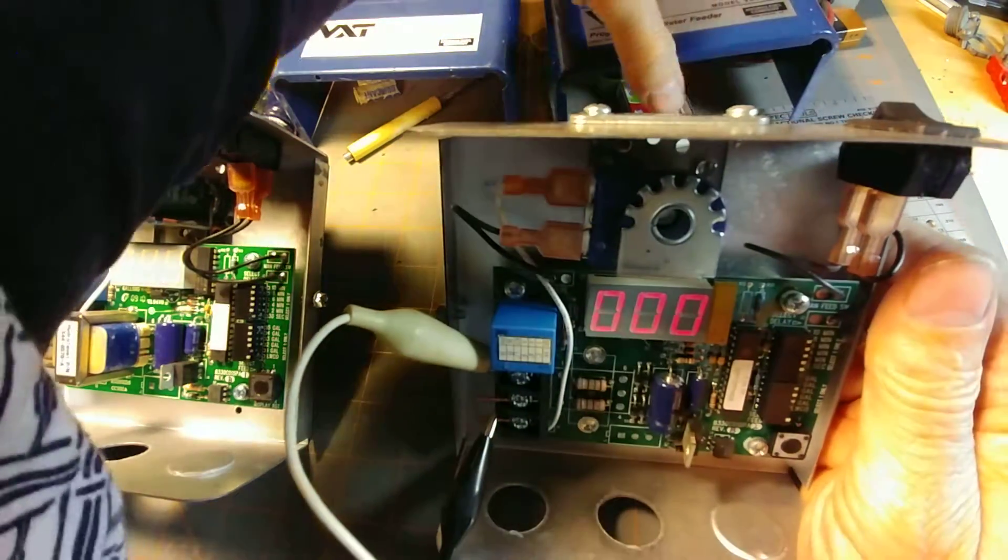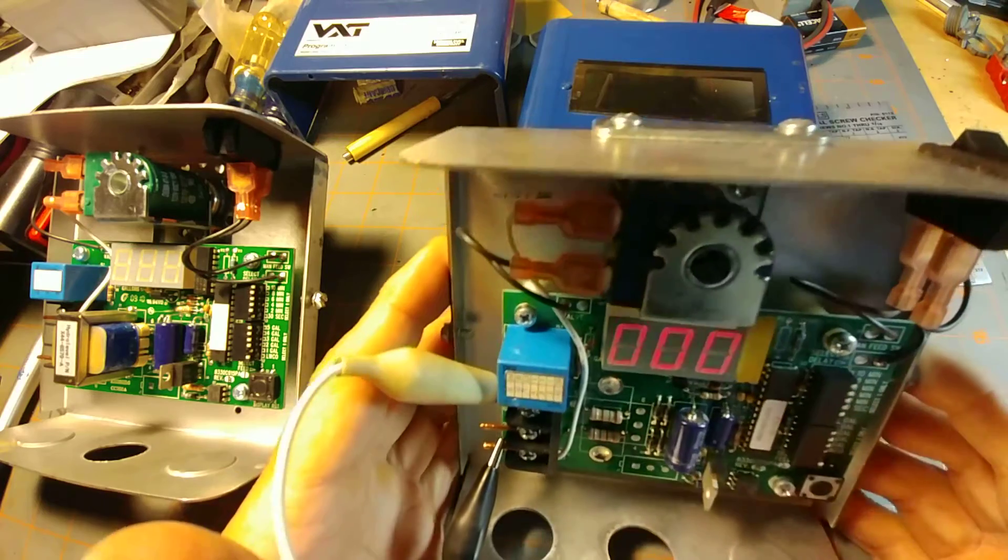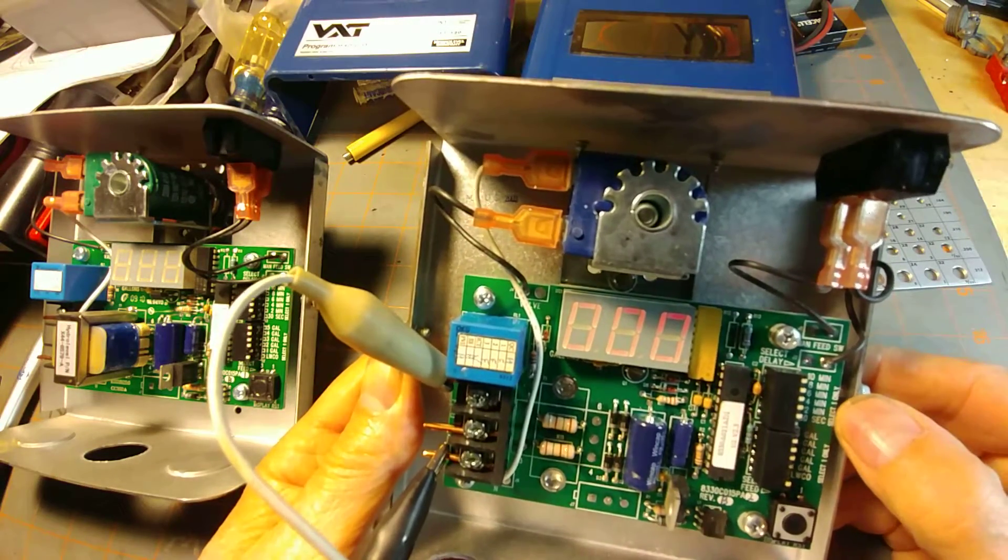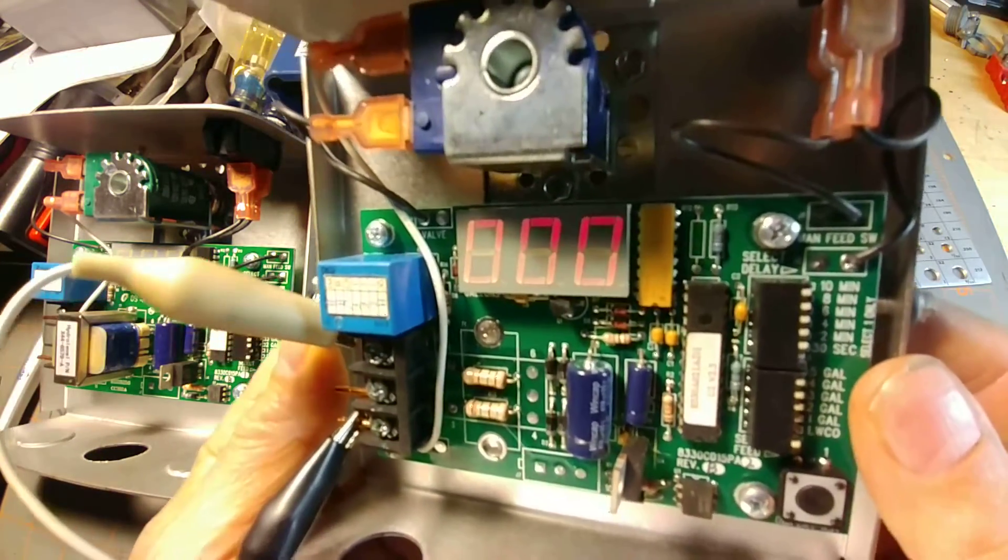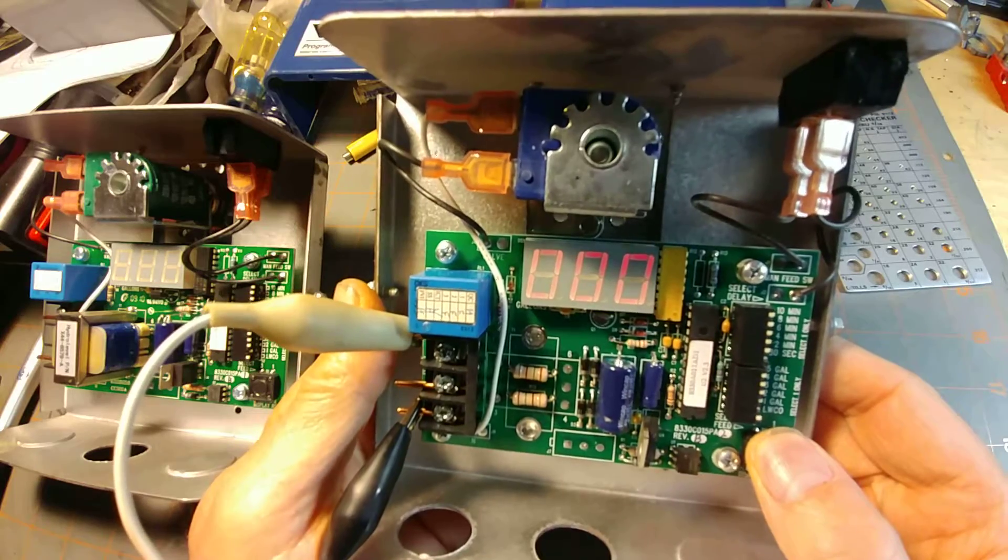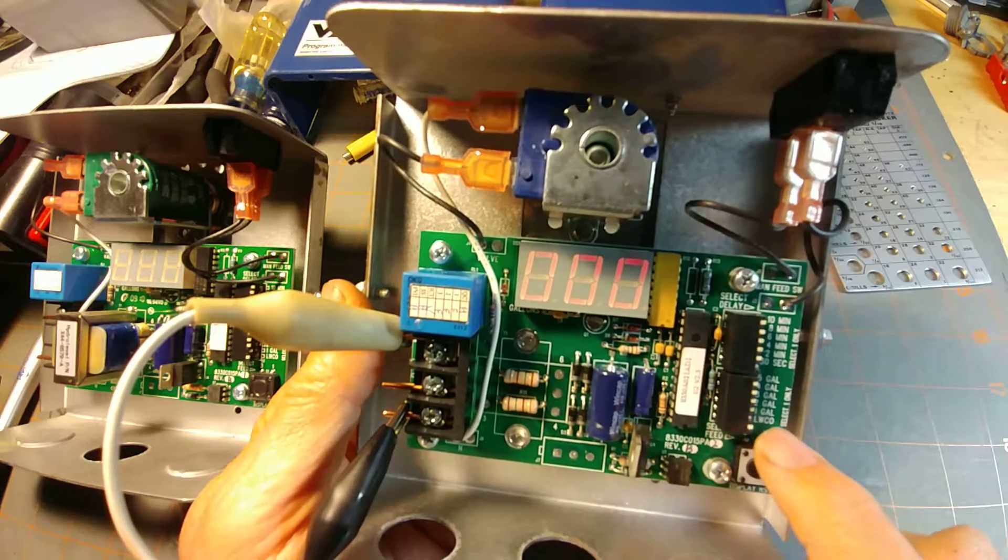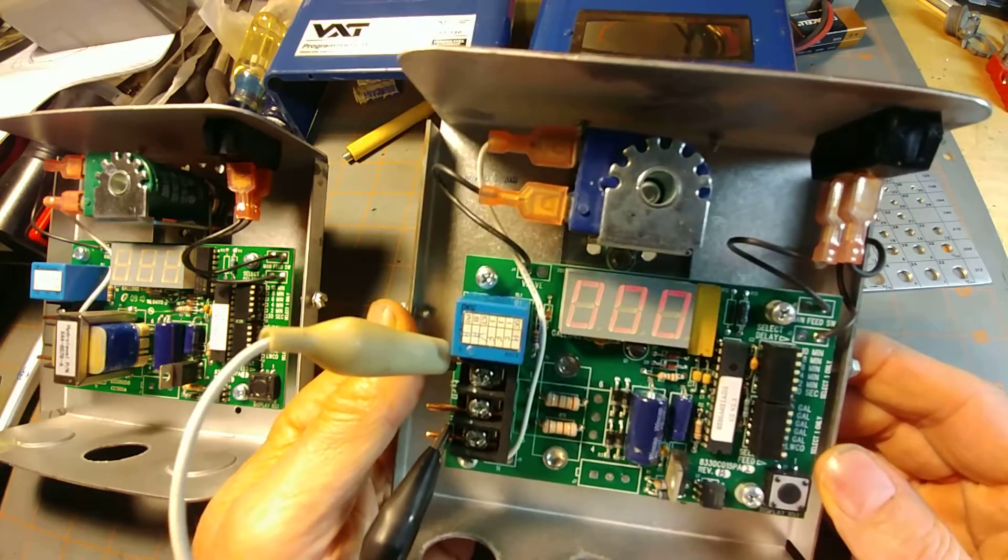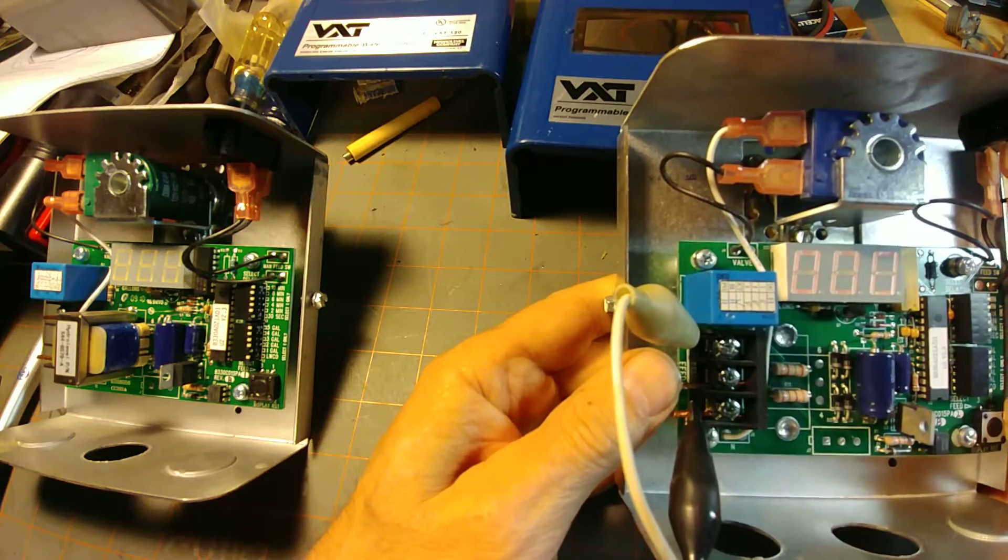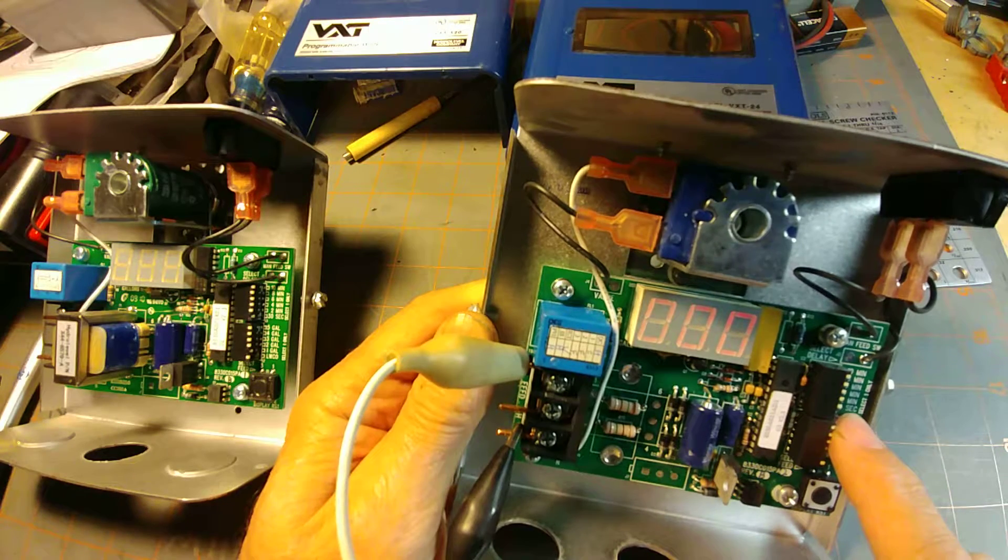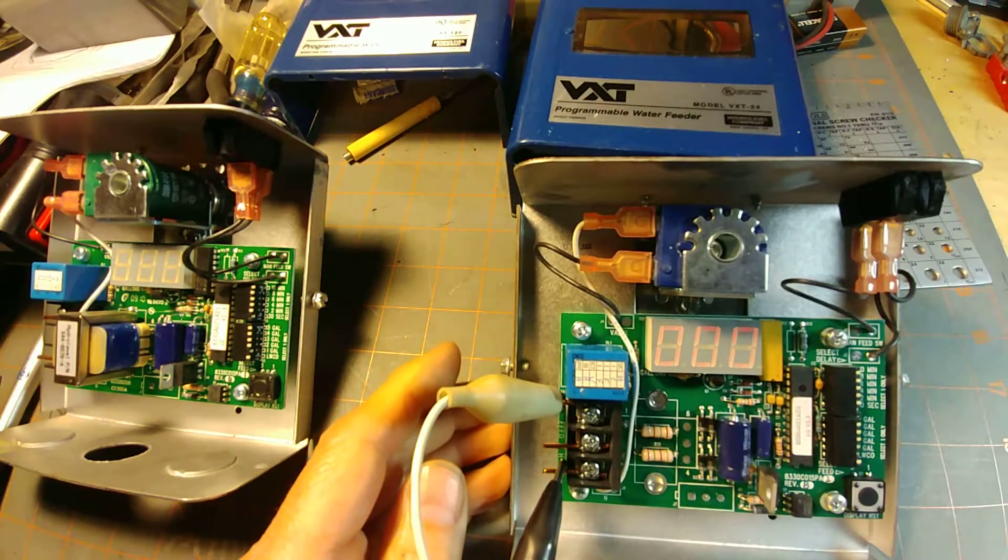Let's see if we can trigger this device. The way you can set it up is by use of these DIP switches. You have delay, and you can set your delay anywhere from 30 seconds all the way up to 10 minutes. Then you can set your feed, what is fed after that delay, either to stop feeding once it hits the low water cutoff level or one gallon all the way up to five gallons. Once it's energized and you send the trigger energy to this feed terminal, it will time out 30 seconds and then stay open for a certain period of time.